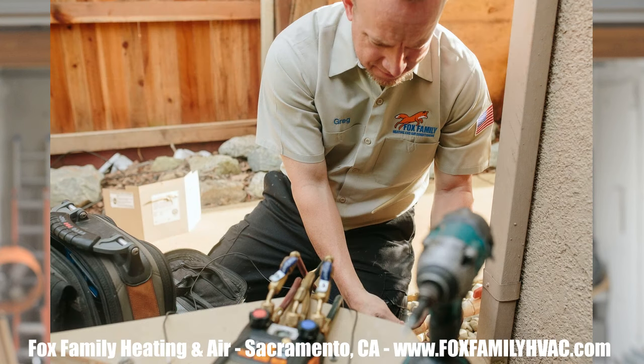If we're going to be using this refrigerant, some things will have to change — most importantly, the residential codes currently in effect. Nothing in them allows for the use of A2L mildly flammable refrigerants in residential cooling systems. Mildly flammable refrigerants can't be used in existing R410A and R22 systems. Compressors have to be upgraded. Systems designed for R454B will require less of a charge than today's R410A systems and will be about 5% more efficient. So if people think they're just going to drop in some XL41 into a R410A system — which does operate at similar pressures — they have some more training to do.